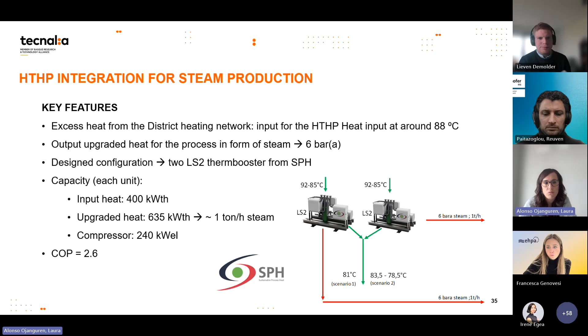Okay, so this is a simplified scheme of the heat pump of SPH. Each of the units includes two compressors in parallel. Also, two evaporators are included. We don't have two evaporators in the scheme. Then we have internal gas heat exchangers as well, and both the evaporators and the gas heat exchangers are plate heat exchangers. And then if we go to the upgraded heat part, we have an inlet of feed water, the same as we would have in a steam boiler.